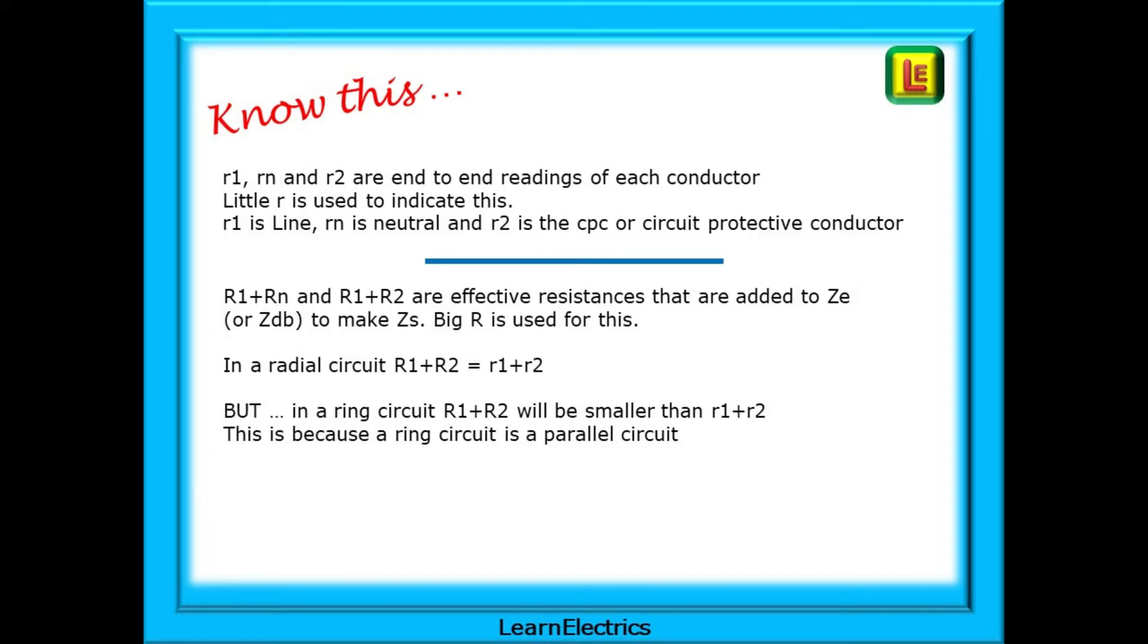In a radial circuit, big R1 plus R2 equals little R1 plus little R2. But in a ring circuit, big R1 plus R2 will be smaller than little R1 plus R2. This is because a ring circuit is a parallel circuit.